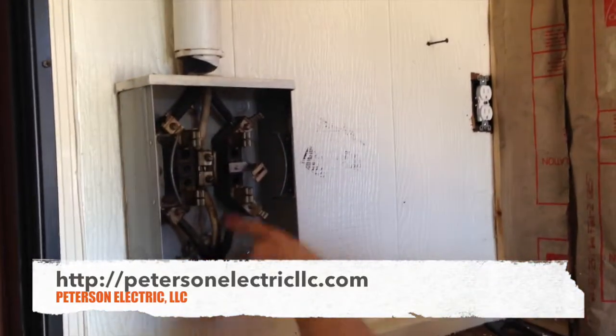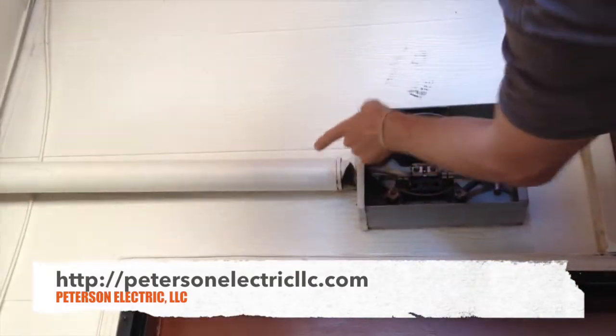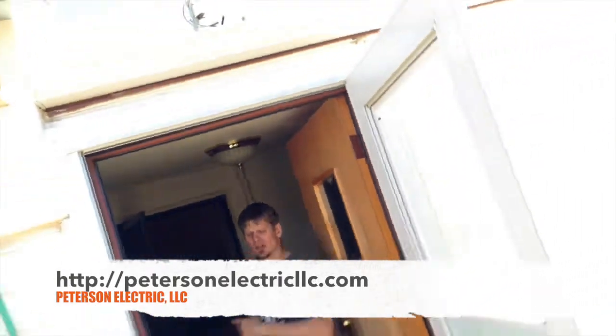Look at the cover right there. This came out to the meter, back to back, and it's a hundred amps going with an overhead service mast with a two-inch pole. Here's the issue: once the power provider came here, this was built as an addition and was not done with a permit — even to his knowledge when he bought the place six months ago. The problem is the power company will not allow you to have a meter on the inside of an addition.